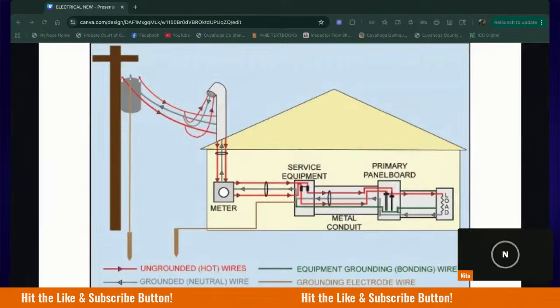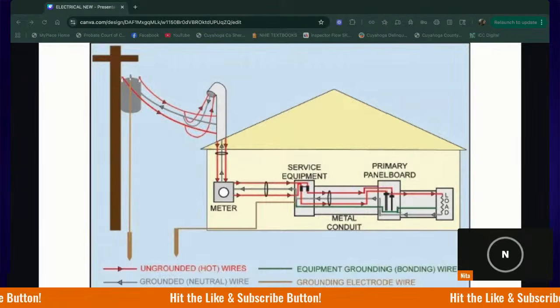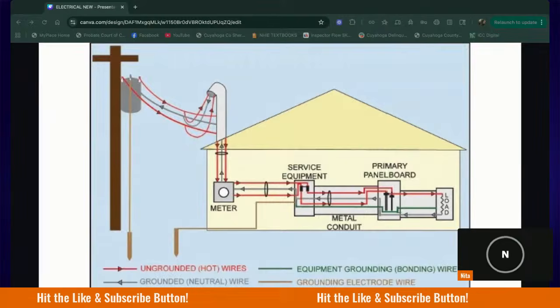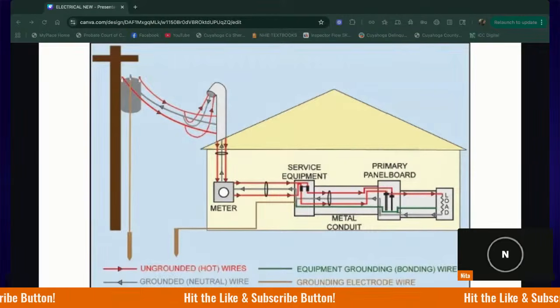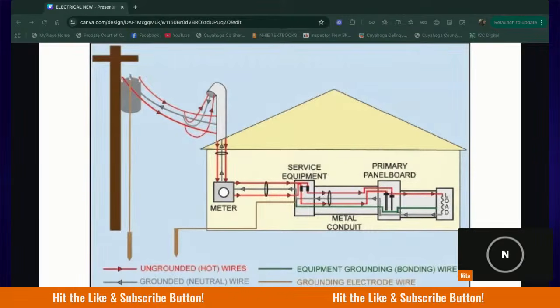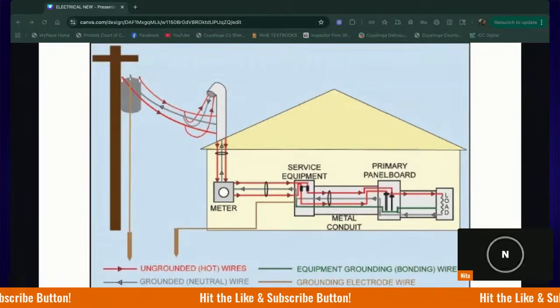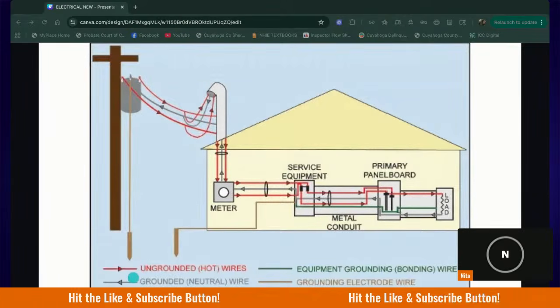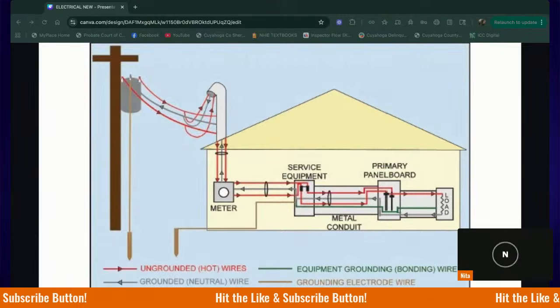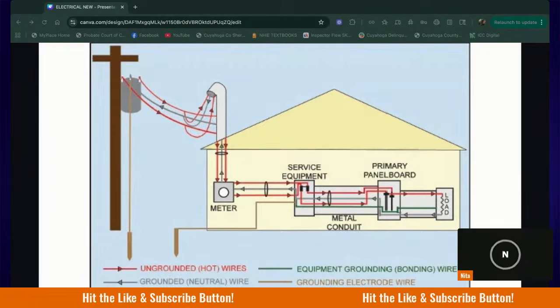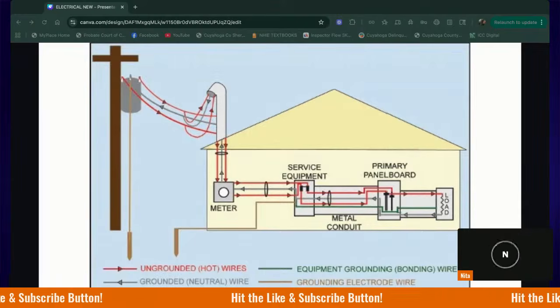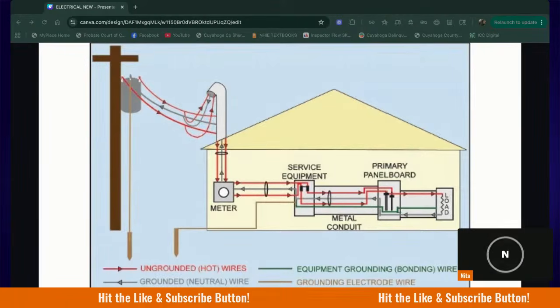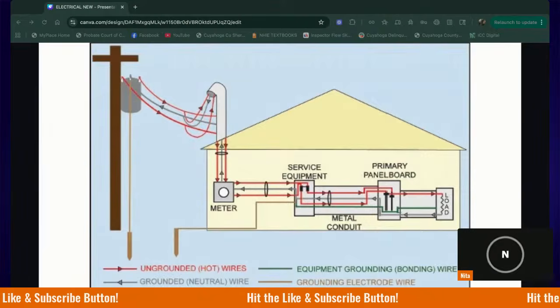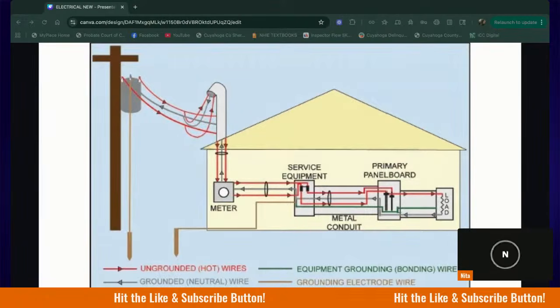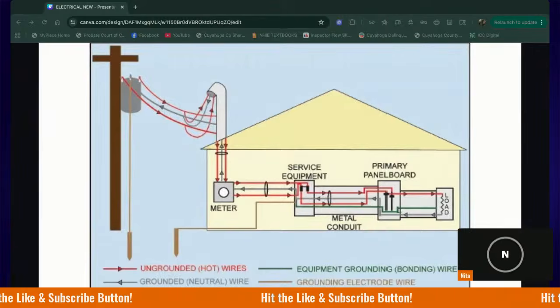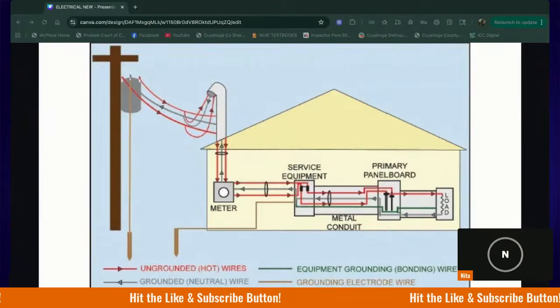Because again, that energy is always going to be flowing and it will look for whatever is conductive. If it's you, if it's a copper plumbing pipe, whatever conductive material it can jump on and travel, it will. And so that's what our EGC is doing, giving a low resistance path for a fault current when there's an issue. Okay. And this path, that's what allows your breakers to trip and prevents other metal parts that you don't want to be energized becoming energized.